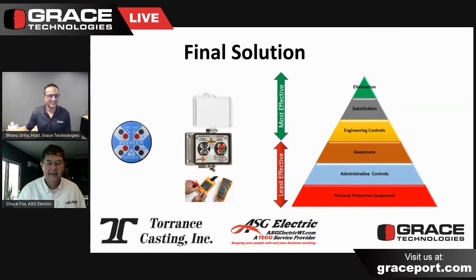And indeed, we worked through all of those issues. One of the other interesting parts of trying to land these various terminations was whether the size of the lug would reduce the gapping distance between different levels of busing, making it easier to trigger an arc flash event by closing the gap in the original engineering busing.